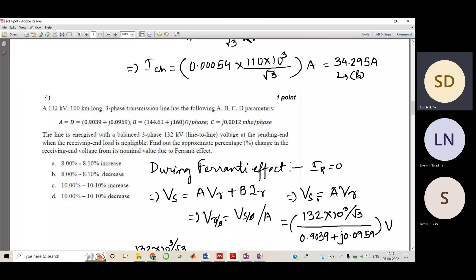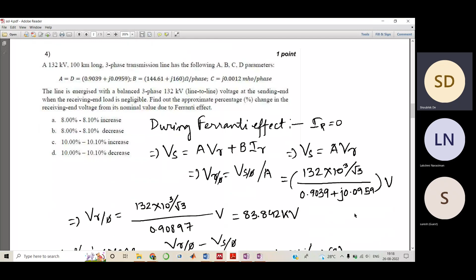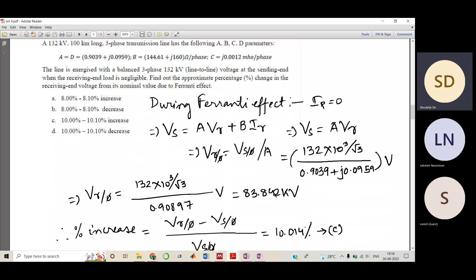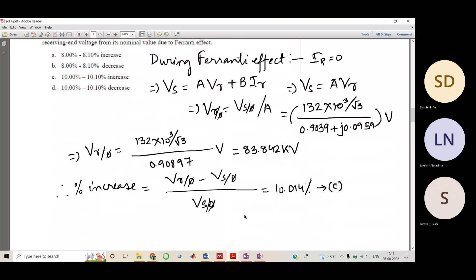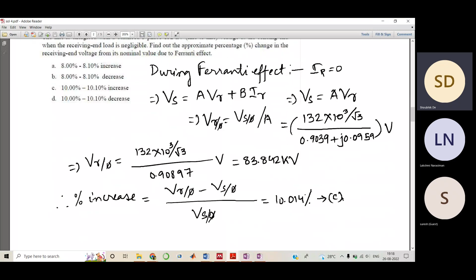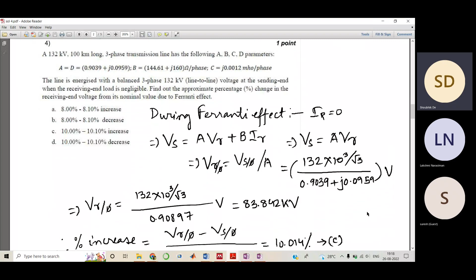We have to calculate per phase only, or it's not strictly required, you can do it in line values too since you just need the percentage change. It's clearly stated that the line is energized with three phase 132 kV at the sending end, so sending end voltage is 132 kV. The A parameter is also given; dividing gives 83.842 as the per phase value, and the difference comes out to 10.014. The denominator should have the sending end voltage, since we're calculating how much the receiving end voltage changes with respect to the sending end voltage. So it comes out to option C, 10.014%. I hope this was clear.